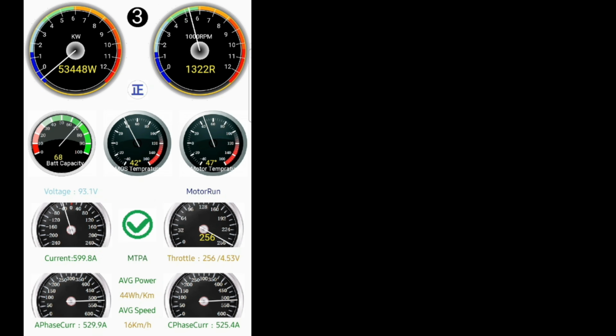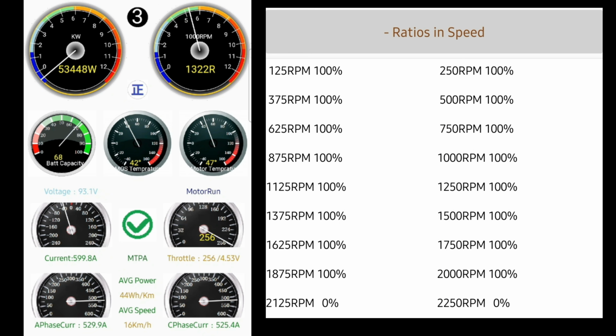I could also limit my phase amps starting at 1000, somewhere right in here. You see when I get to about 1250 here on the RPM, phase amps are at 554. So if I want to limit with phase amps, I've got to go to ratios in speed, and I've got to lower the percent of phase amps that's available. 554 divided by 1200 is 46%. I want to be less than 46%. So by 1200 RPM, I want to be around 40%. Again, making that up. We'd have to test it after we do it.